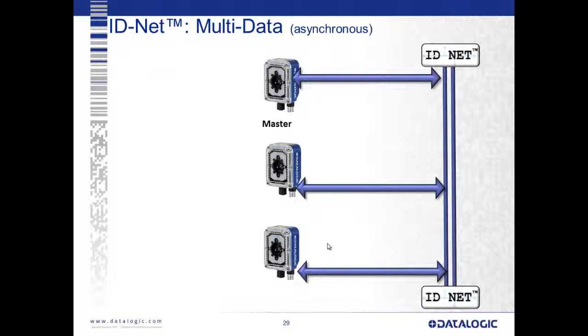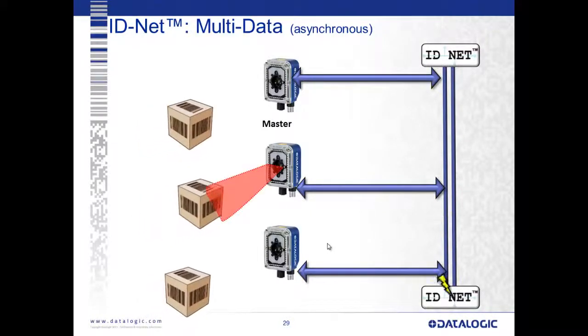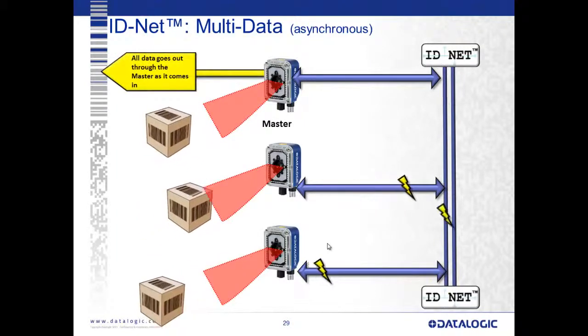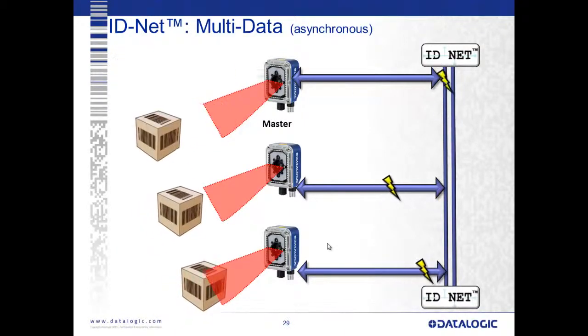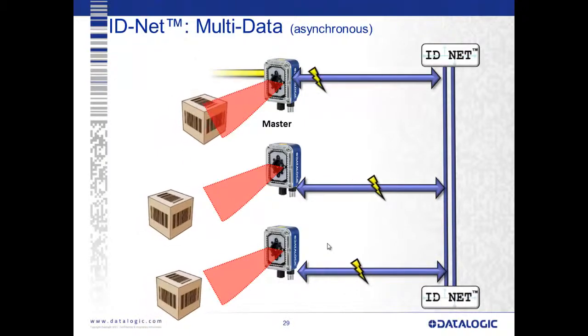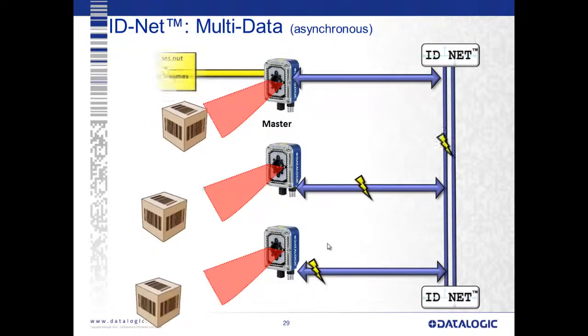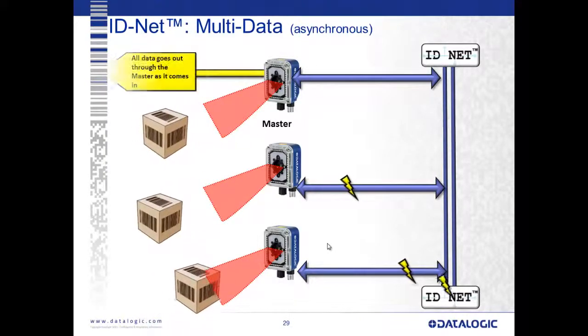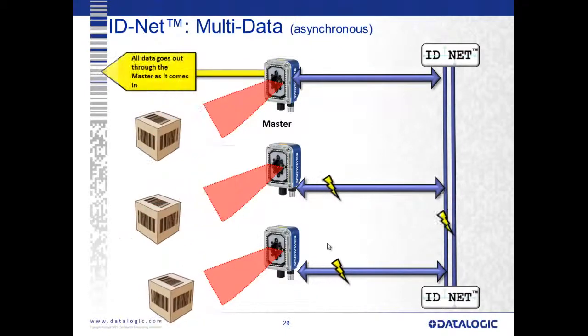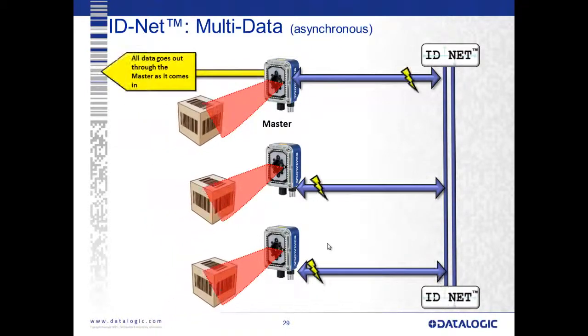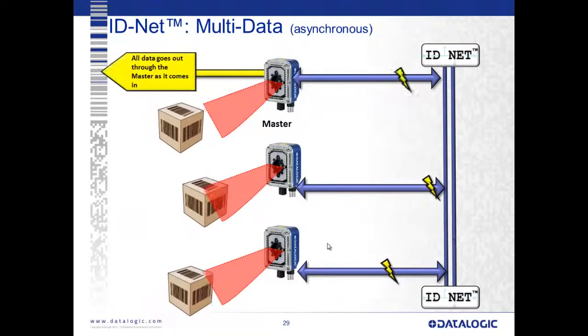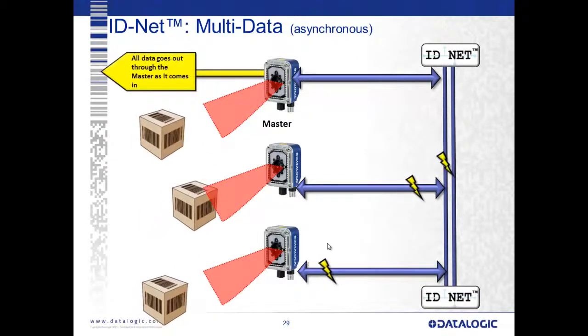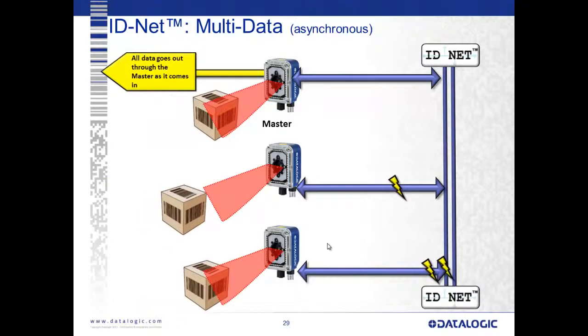Here's an asynchronous system, or multi-data IDNet network. Same hardware configuration, just a quick software parameter change. Now, as objects come in to each device, they're triggered individually and send data back to the host through the IDNet network, generally with an address prefix to let it know which device it came from. This allows you to multiplex the system together and have one data communication point back to your host system, whether it's a PC or a PLC, so you only have to manage one single data set.